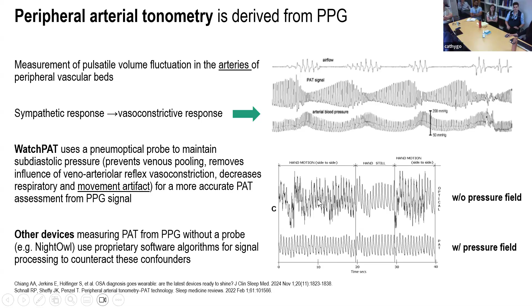Without that probe, you can have venous pooling, veno-arterial reflex vasoconstriction, respiratory and motion input, all causing artifact. So by having that probe, your ability to get an accurate PAT assessment from the PPG signal is improved. Now, we're going to talk about a bunch of the new home sleep apnea tests, and you'll see that they all measure PAT, but there's no probe involved. That's because they're just using algorithmic processing to remove artifact from that PPG-derived PAT. And you can see, this is someone moving their hand around, their hand is still here, they're moving their hand around again. And this is their PAT derived from photoplethysmography with the pressure field and without. So you can see all of that movement artifact that's prevented by having that pneumatic probe.